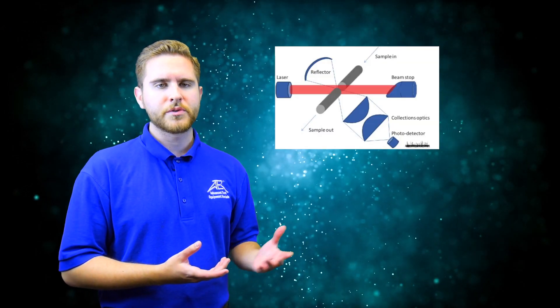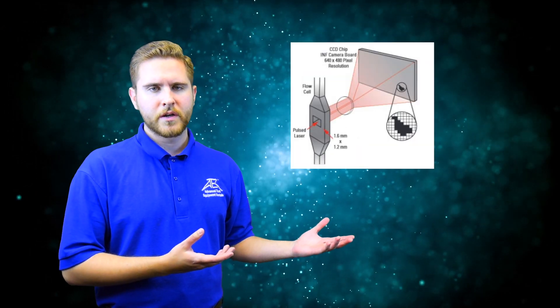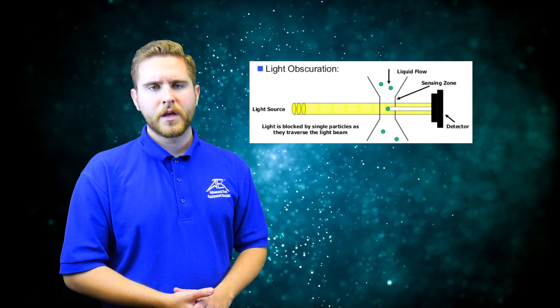An air particle counter diagnoses indoor air quality by counting and sizing air particles in controlled spaces. Particle counting is performed with the principles of light scattering, direct imaging, or light obscuration. The particle sample is passed through a detection chamber, and as it passes, a high intensity light source illuminates the particle with one of these three methods.